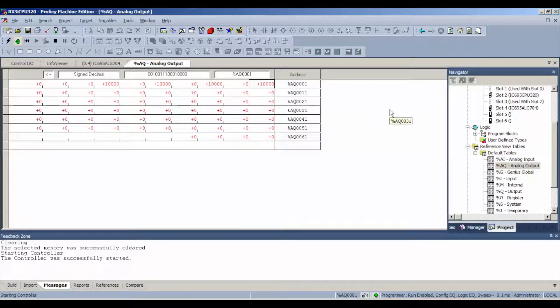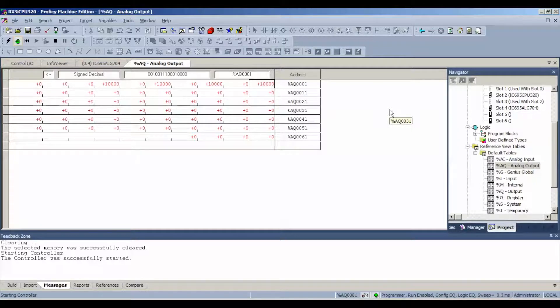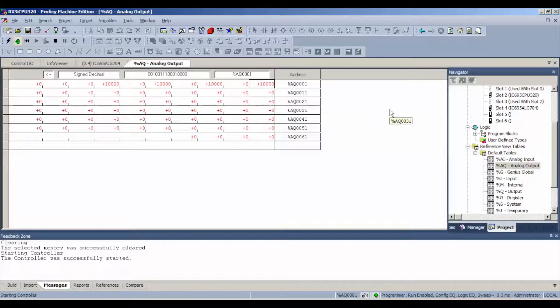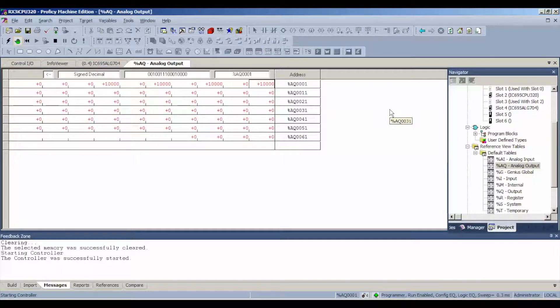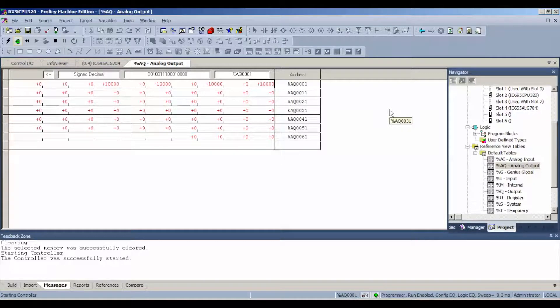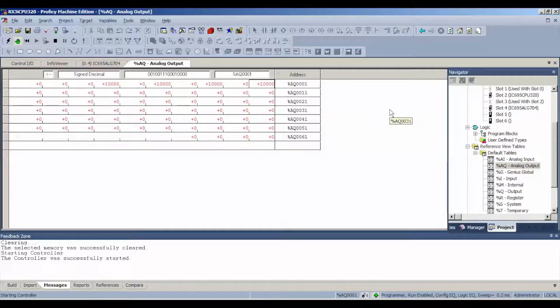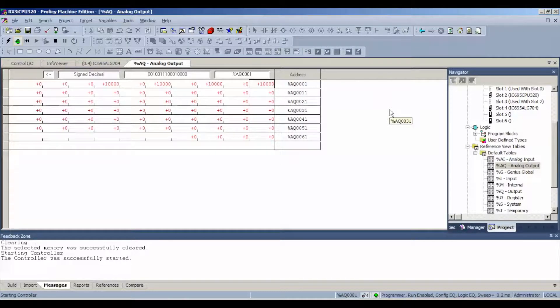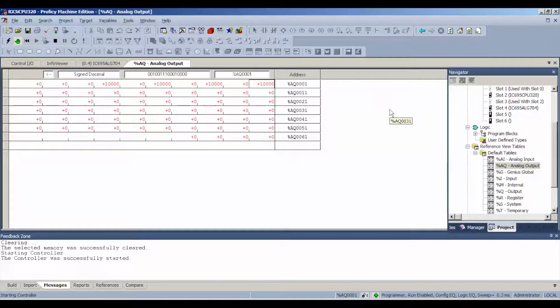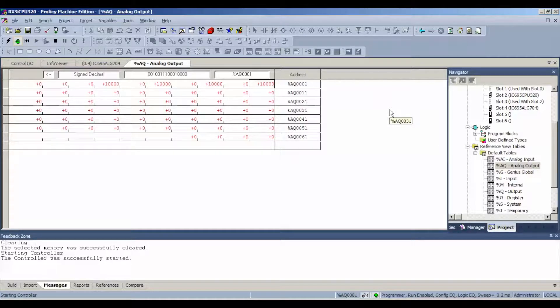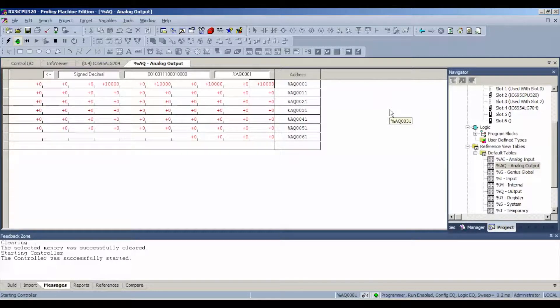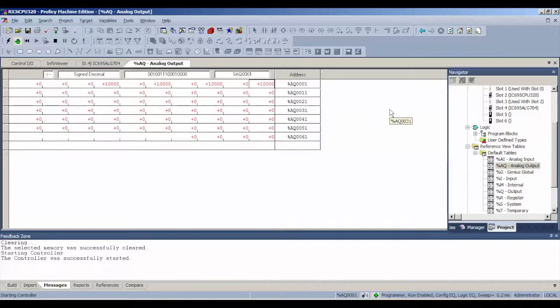So I'm in run mode, I've got values that are set, and I want to probe these terminals. Now the way these channels are set up on the terminals is that there's three screws per channel. The outermost two screws are for voltage, and the inner lowermost screws or terminals are for measuring milliamp.